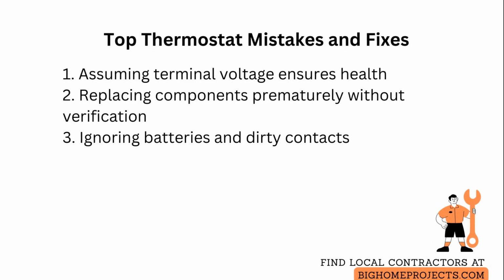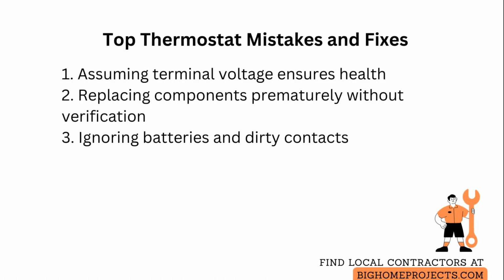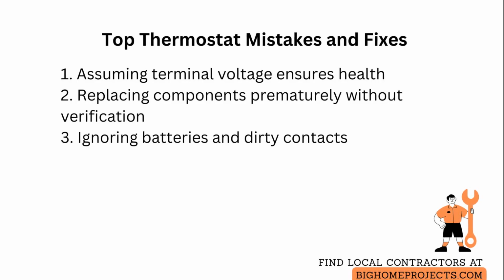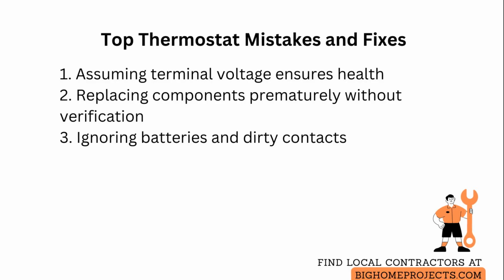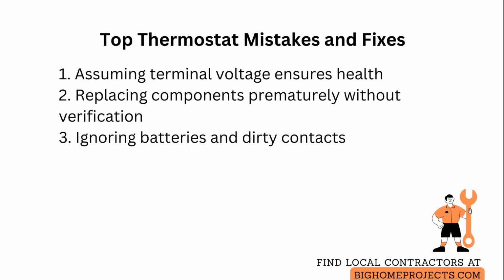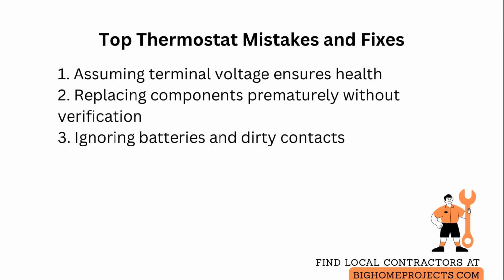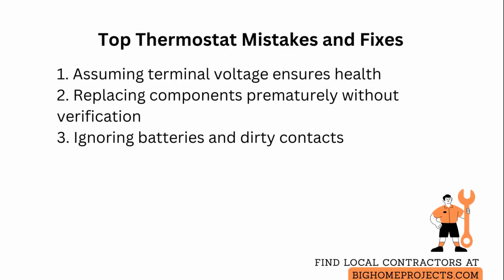Common mistakes include assuming correct terminal voltage guarantees thermostat health. The solution is to perform bench power tests and inspect internal components before declaring the control board faulty. Another frequent error is replacing wiring or the furnace control board prematurely.